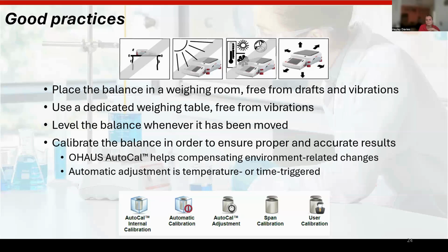No problem. Okay, so place the balance in a weighing room free from drafts and vibrations. Try to use a dedicated weighing table if you can. If you have one of the high-end 4 or 5 decimal place balances, you may have seen the big marble slabs and marble weighing tables. That is to absorb any little vibrations. Level the balance, if it can be leveled, whenever it's been moved, because we need to make sure the balance is level to get accurate results.